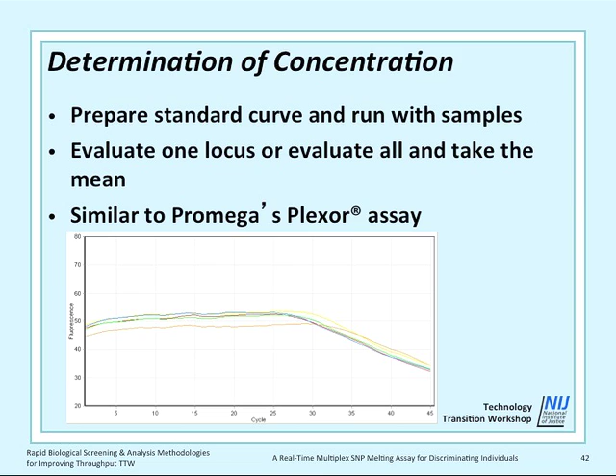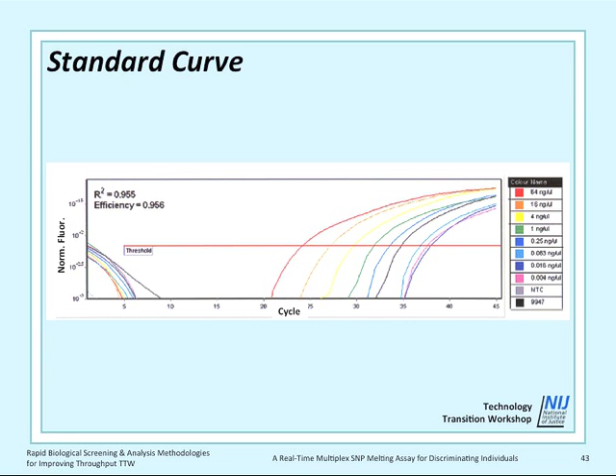As discussed earlier, the assay can also be used to measure concentration of the extracted samples. Similar to how Promega's Plexor assay works, the fluorescence decreases as PCR product increases. Standard curves can be run and quantitation performed similarly to what most laboratories do today. This slide shows the quantitation results of 2 quadruplex assays. The values in the bottom table represent the calculated concentrations based upon the standard curve results using that locus. 2 loci are highlighted for an example.